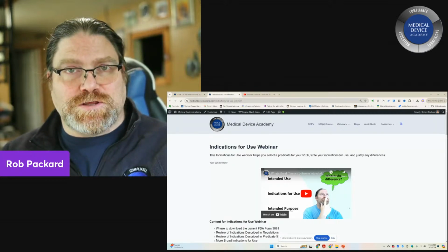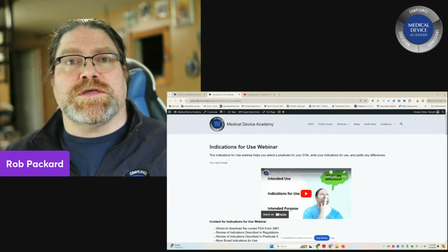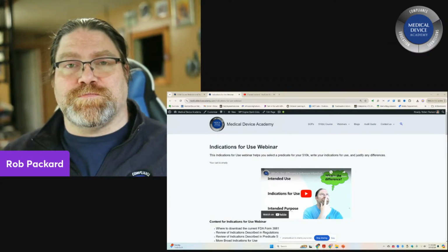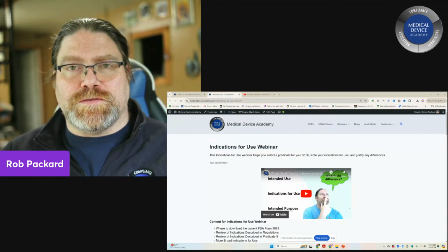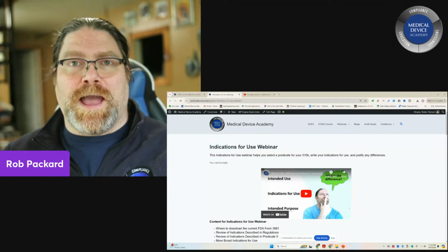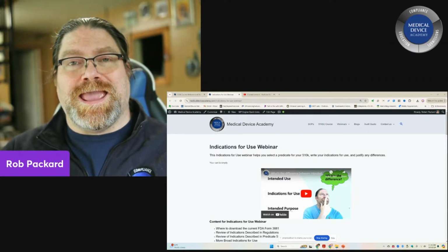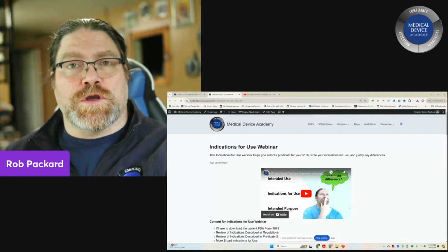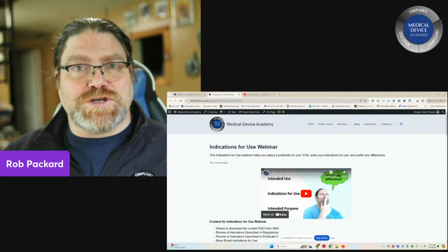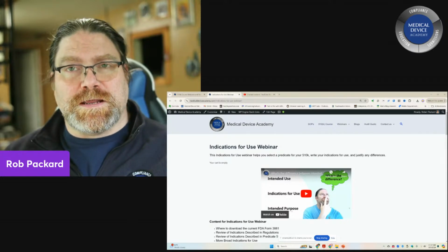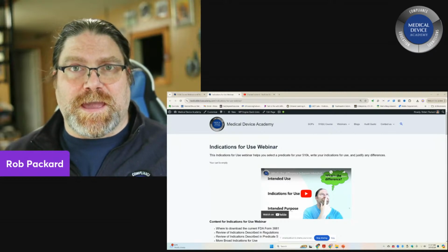First, intended use. A lot of people get confused between intended use, indication for use, and intended purpose. And we're going to explain when each one is relevant. We've done this before, but we're going to include this in our webinar about how to write an indication for use for a 510K submission and how that's different from your approach that you would use for a de novo submission. We're also going to explain how to write a justification for any differences between your indication for use and the indication for use in your predicate device if you're submitting a 510K.